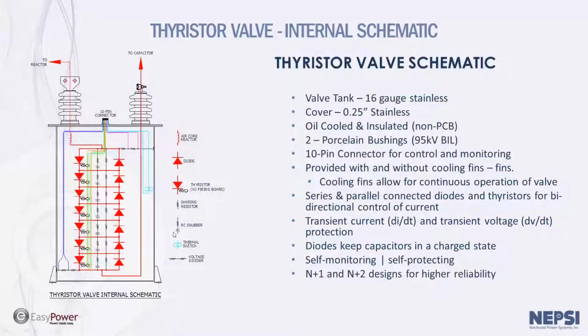Internally, this valve consists of SCRs in one direction, diodes in the other direction, and it's a 2-bushing device. We have voltage sensors on the inside in the form of voltage dividers for sensing voltage. We also have thermal sensors in here for sensing temperature. So it's a self-protected device. We have a 10-pin connector up on top for connection to the control.